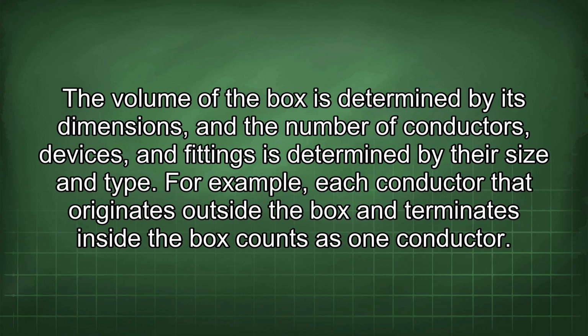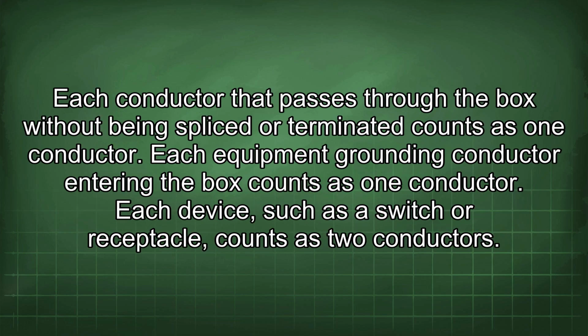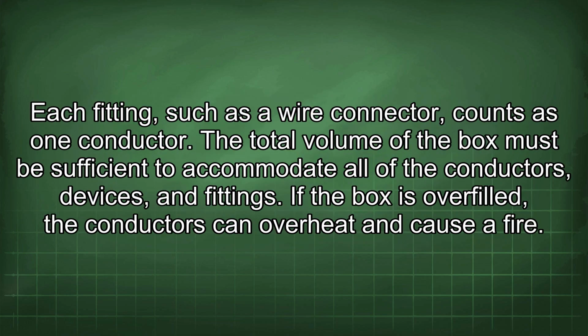For example, each conductor that originates outside the box and terminates inside the box counts as one conductor. Each conductor that passes through the box without being spliced or terminated counts as one conductor. Each equipment grounding conductor entering the box counts as one conductor. Each device, such as a switch or receptacle, counts as two conductors. Each fitting, such as a wire connector, counts as one conductor. The total volume of the box must be sufficient to accommodate all of the conductors, devices, and fittings.